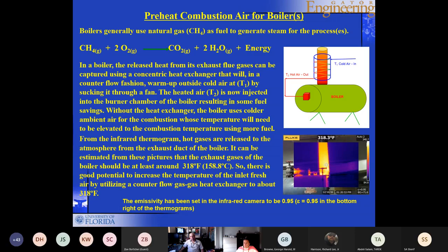Here's a picture of what our infrared camera is showing, and you will see that there's a temperature of 218.3 degrees Fahrenheit that is existing at the surface of the boiler, or 318 rather, and that tells you that is the ideal temperature that the air should be preheated to. In other words, we could get to that point without violating the second law of thermodynamics, if you like to think of it that way. Of course, we're burning methane. This is the chemical equation for that. You produce carbon dioxide and water vapor and energy. It's an exothermic reaction that releases heat.